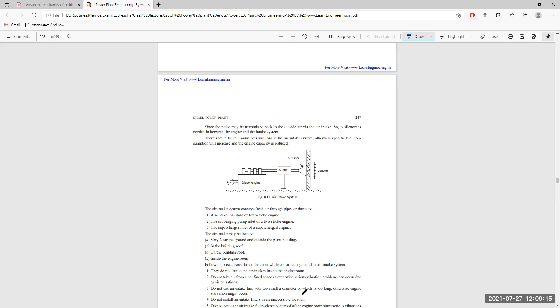Do not take air from a confined space, otherwise serious vibration problems may occur due to air pulsation. Do not use an air intake line with too small a diameter or too long, otherwise engine starvation may occur. Do not install air intake filters in an inaccessible location. Do not locate the air intake filter close to the roof of the engine room, since serious vibration of the roof may occur.